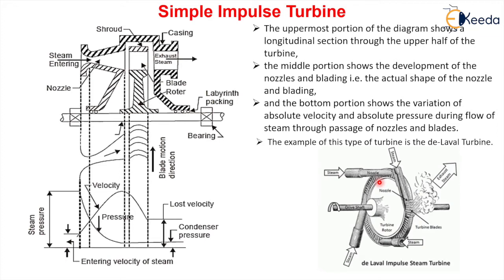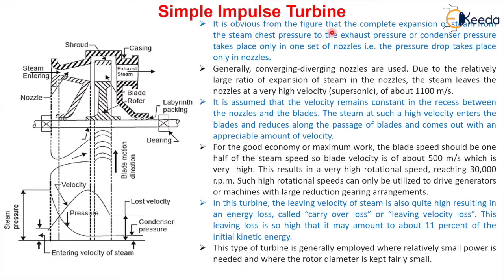It is obvious from the figure that the complete expansion of steam — from the steam chest pressure (boiler pressure) to the exhaust or condenser pressure — takes place only in one set of nozzles. Pressure drop takes place only in the nozzle. Generally converging-diverging nozzles are used due to the relatively large ratio of expansion. The steam leaves the nozzle at a very high velocity — about 1100 meters per second, which is supersonic.